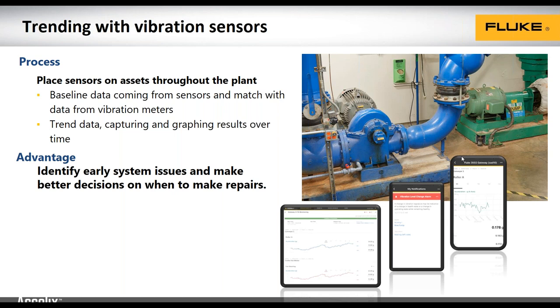The next question: do the gateways work off Wi-Fi only? The sensors use Bluetooth Low Energy to send the signal from the sensor to the gateway, and then the gateway uses Wi-Fi to get it up to the cloud. If you're in a location without a good Wi-Fi signal, you can add a Wi-Fi extender. In a boiler room or basement area with many machines, you may only need one or two Wi-Fi access points to handle all the gateways and sensors.